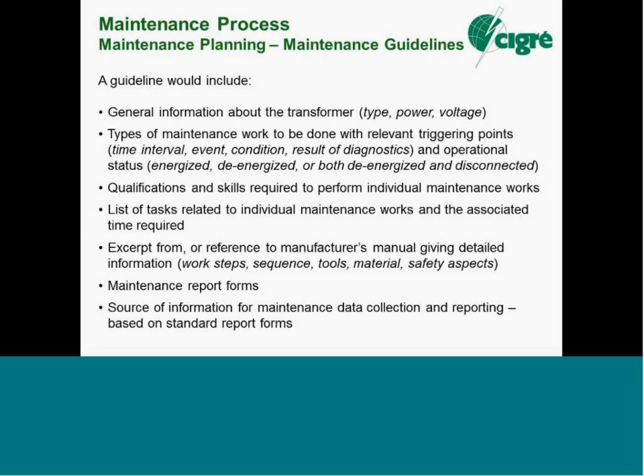So high danger to certain transformers. If we were to monitor this, we'd take an oil sample and do the corrosive sulfur test for copper sulfide, but we should now also be adding the DIN standard, DIN 51353, I think it is, for the silver strip test to see if it will actually tarnish silver and form silver sulfide. It's probably enough on that topic that we can afford at the moment, but have a look at technical brochure 378 for further reading.